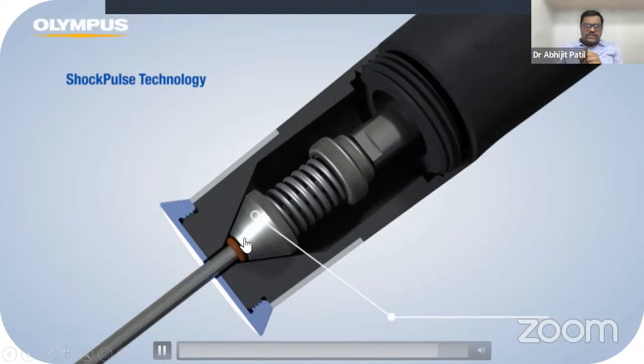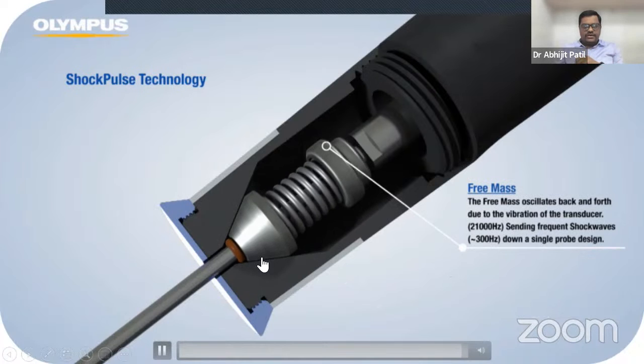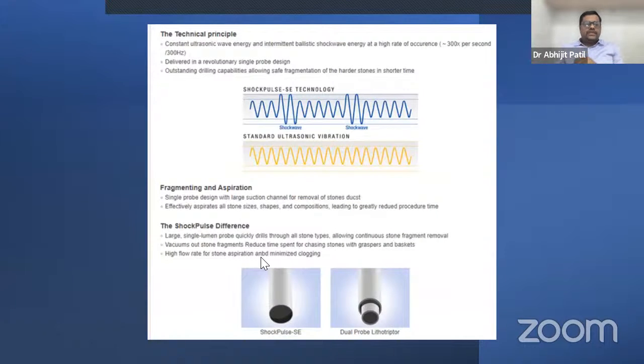So this is the return spring. This is essential to cause the high wave ballistic component in the shock pulse. Now, this large single lumen probe quickly drills through all types of stones, allowing continuous stone fragment removal. It vacuums out stone fragments, which reduces time spent chasing stones with graspers and baskets. It has a high flow rate for stone aspiration and minimizes clogging. As I initially showed, if you have a dual probe lithotripter, this is the area where you achieve the stone fragments, versus the shock pulse, where this complete probe works in itself.